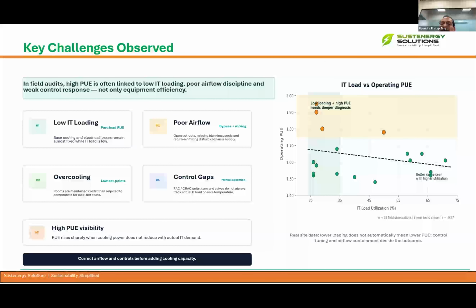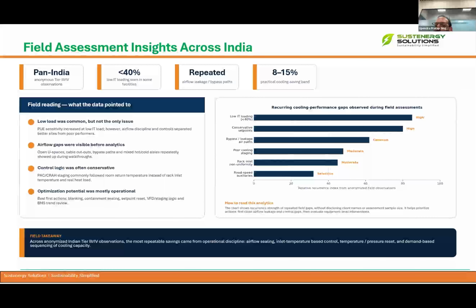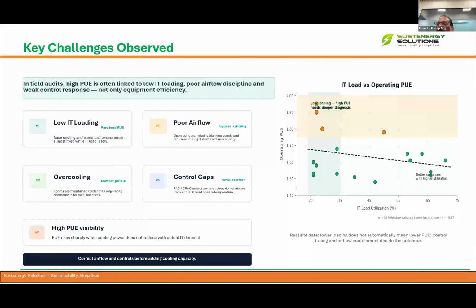Then control is very important because now we are coming with the BMS to sequence the units and maintain the temperatures. So that control logic is also very important, and the sequencing of our units. Which unit needs to run first, which needs to run second. First we need to understand the operating efficiencies of those units, and then we can properly design the sequence of operations. That's how we are going to plan these coming data centers. So lower loading does not automatically mean that there is a lower PUE only due to loading. Control tuning and other airflow containment also decide how much PUE we are going to maintain.